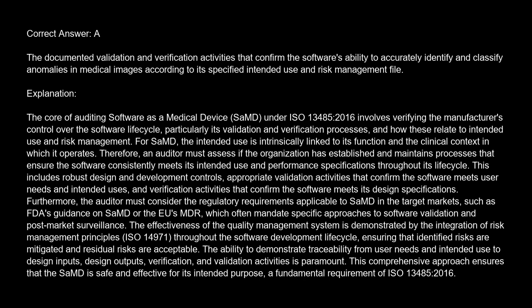For SaMD, the intended use is intrinsically linked to its function and the clinical context in which it operates. Therefore, an auditor must assess if the organization has established and maintains processes that ensure the software consistently meets its intended use and performance specifications throughout its lifecycle. This includes robust design and development controls, appropriate validation activities that confirm the software meets user needs and intended uses, and verification activities that confirm the software meets its design specifications.